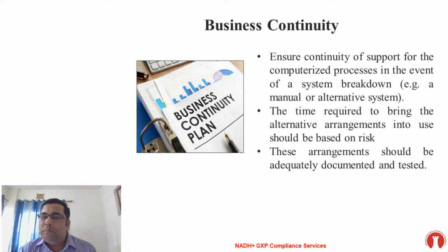Mr. Manoj is asking one more question: due to any reason, if the computer operating system changes, does the existing software need to be requalified? Yes, if the operating system is changed, I need to qualify my software, because that software is installed on the same computer system. The qualification or validation of my software of interest, the depth of validation, should be based on the impact of changing my operating system.